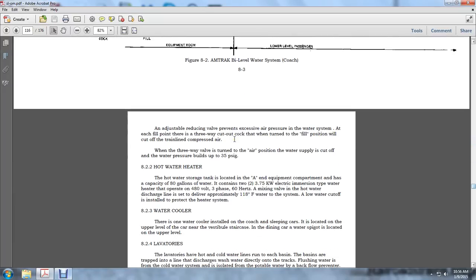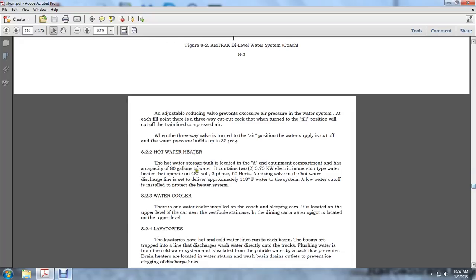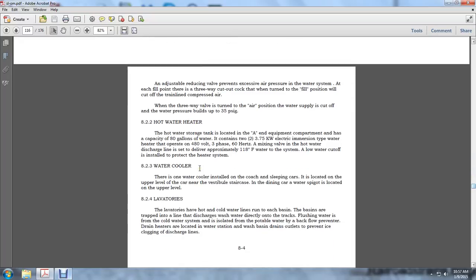8.2.2, the hot water heater. The hot water storage tank is located in the A end of the equipment compartment, with a capacity of 80 gallons of water, and contains a 3.75 kilowatt electrical immersion type heater operating at 480 volt, 3 phase, 60 hertz. A mixing valve at the hot water discharge delivers approximately 118 degrees Fahrenheit water to the system. A low water cutoff is installed to protect the heater system.